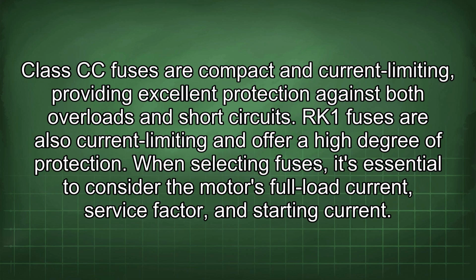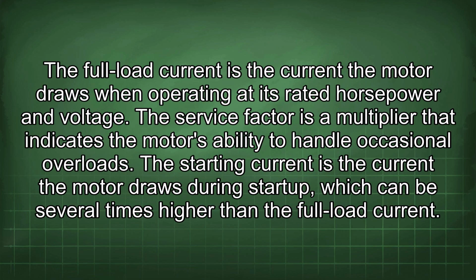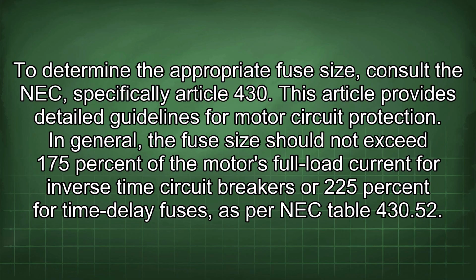When selecting fuses, it's essential to consider the motor's full load current, service factor, and starting current. The full load current is the current the motor draws when operating at its rated horsepower and voltage. The service factor is a multiplier that indicates the motor's ability to handle occasional overloads. The starting current is the current the motor draws during startup, which can be several times higher than the full load current. To determine the appropriate fuse size, consult the NEC, specifically Article 430. This article provides detailed guidelines for motor circuit protection.